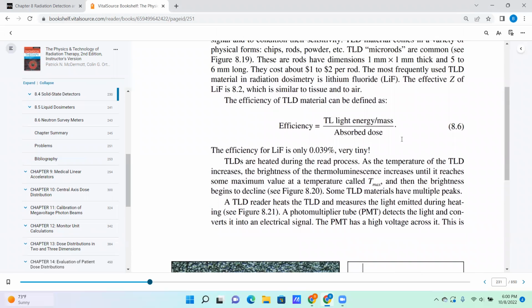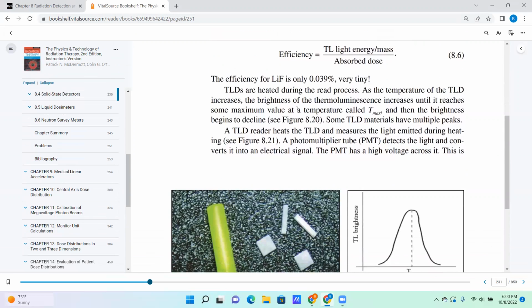So the efficiency of TLD material can be defined as the TLD light energy per mass divided by the absorbed dose. The efficiency for lithium fluoride is pretty low, so it's very tiny. They're heated during the read process. As the temperature of the TLD increases, the brightness of the thermoluminescence increases until it reaches some maximum value at a temperature called Tmax. And then the brightness begins to decline.